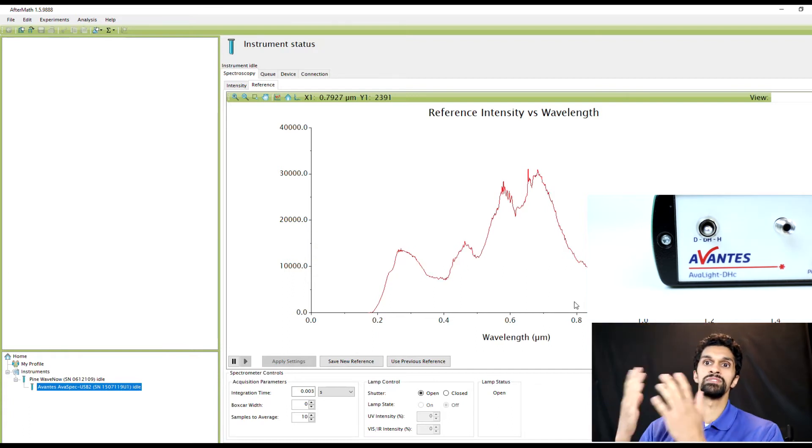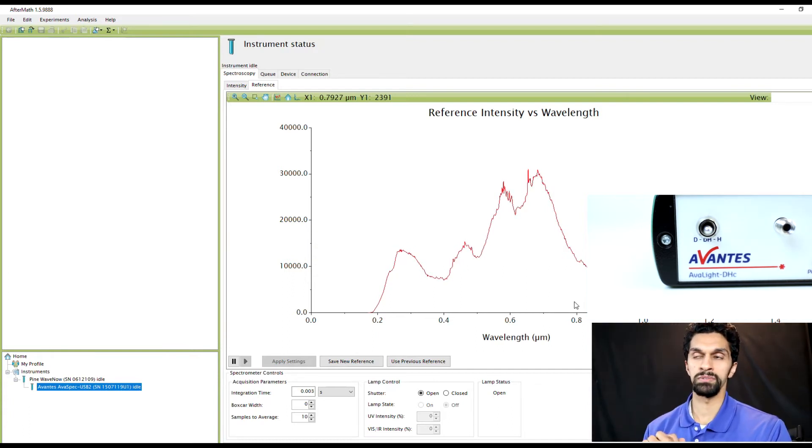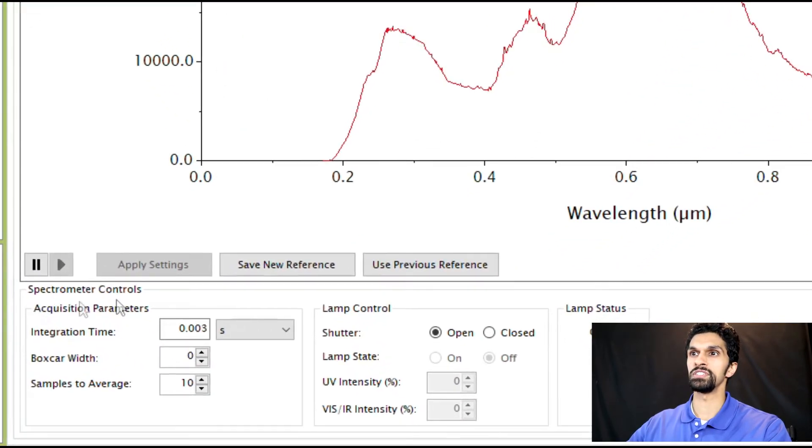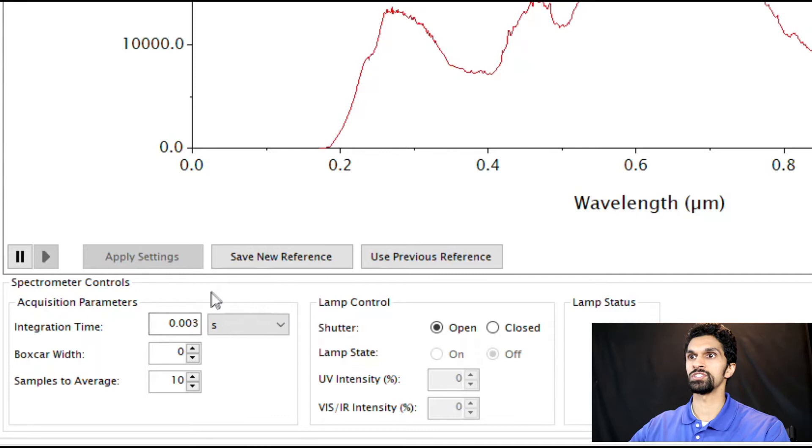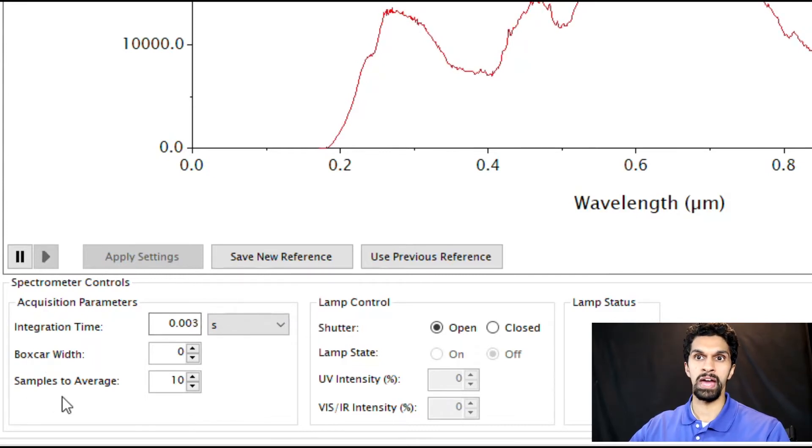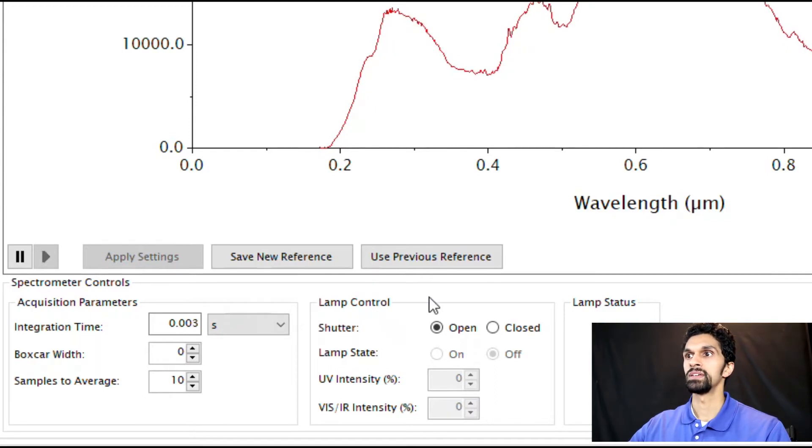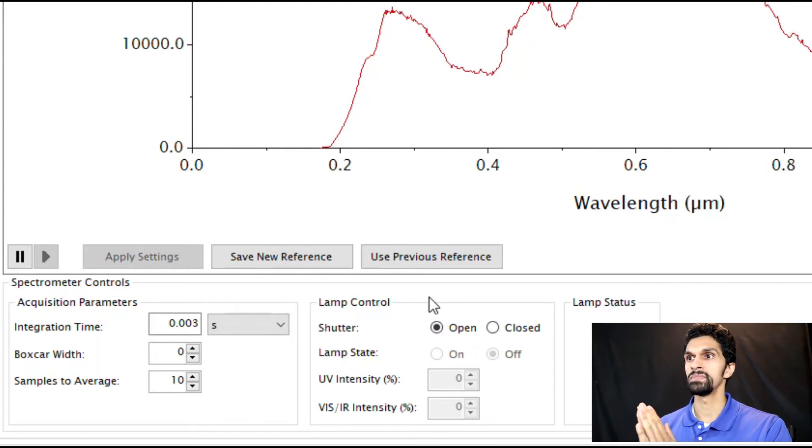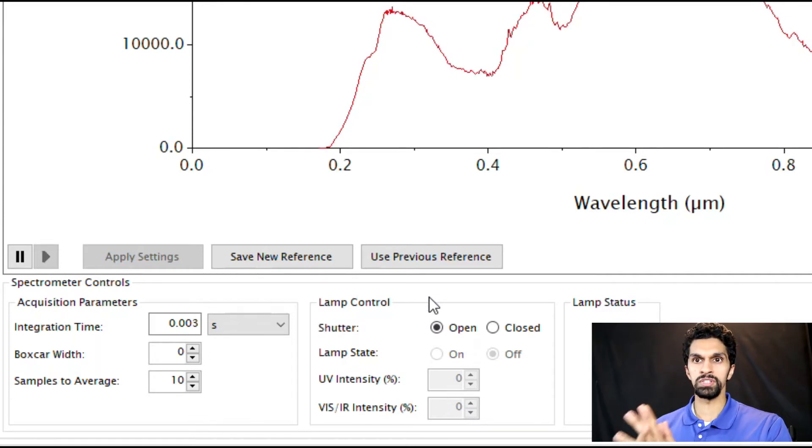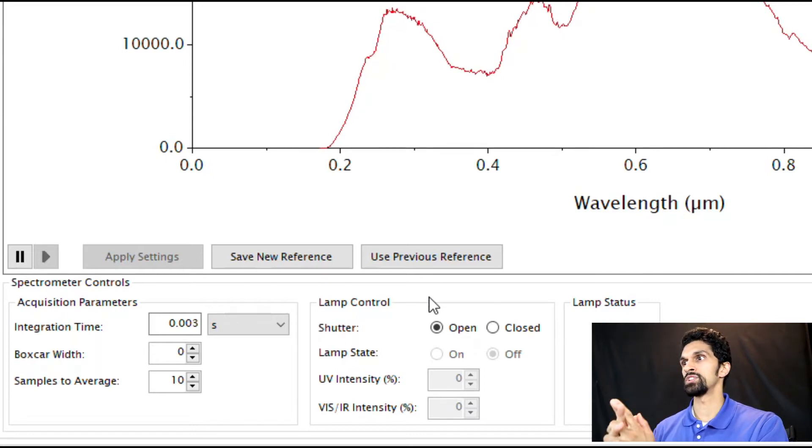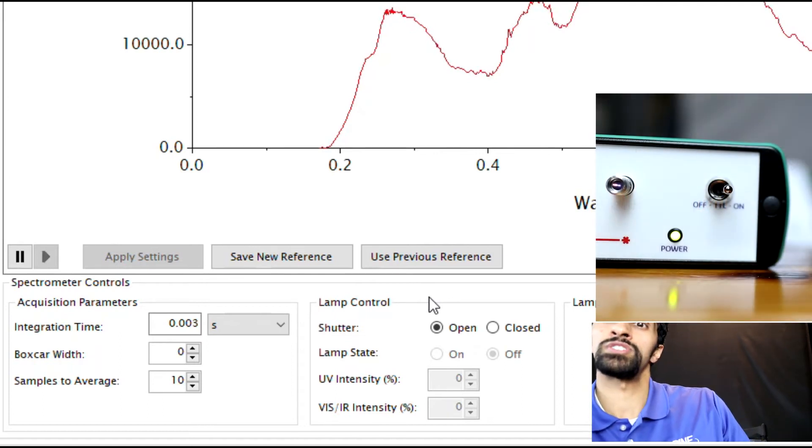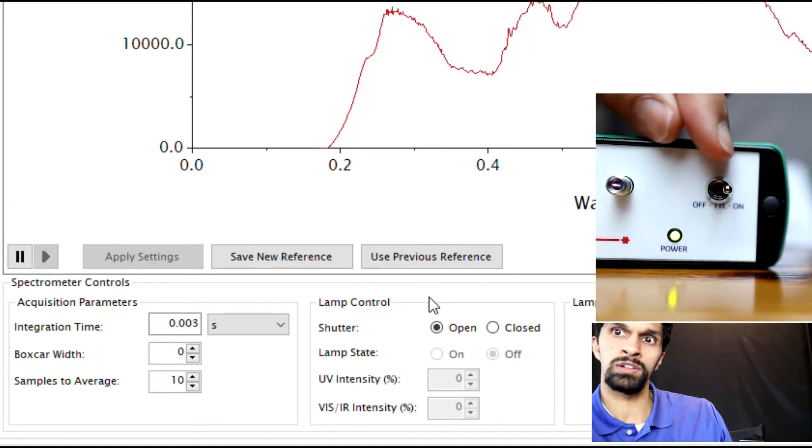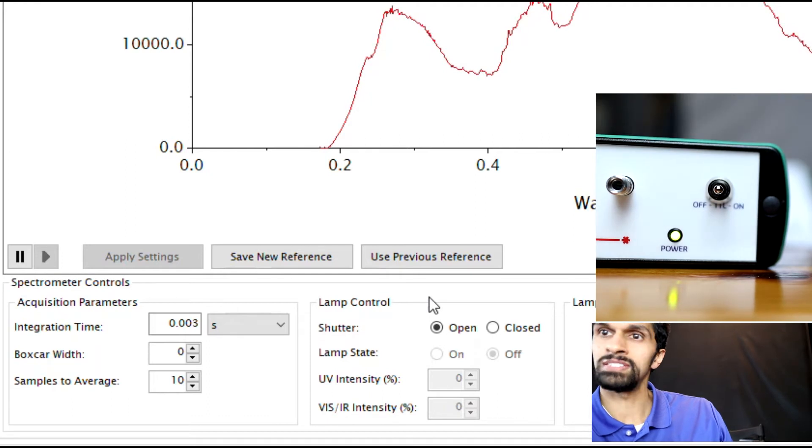If you go to the bottom of the screen you'll see the spectrometer controls. You can adjust the acquisition parameters such as the integration time, the boxcar width, as well as the number of samples to average. On the right hand side you can see the lamp control. The lamp control allows you to turn the shutter of the lamp on and off. If you want to use the lamp control, the lamp needs to be set to TTL and I'm showing a small inset here. I'm going to reach over. Instead of it being set to on or off, I'm putting it in the middle and it is set to TTL.